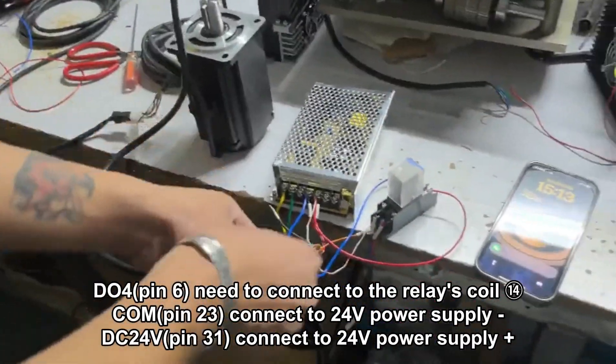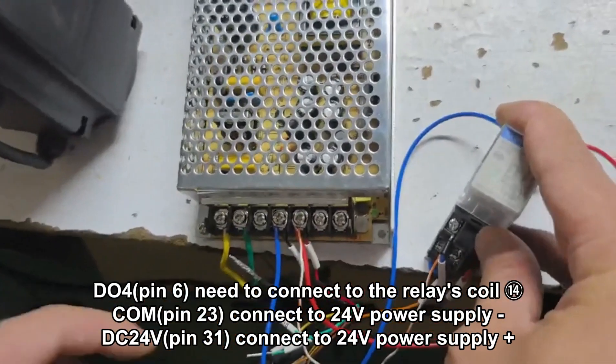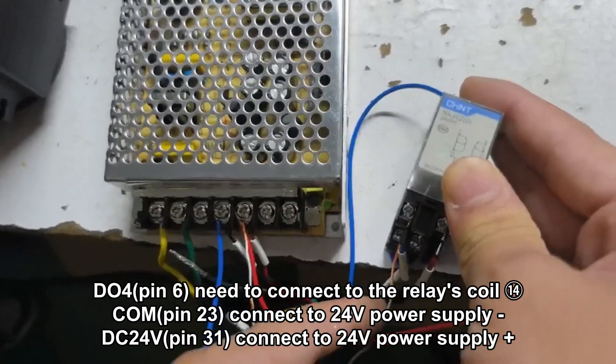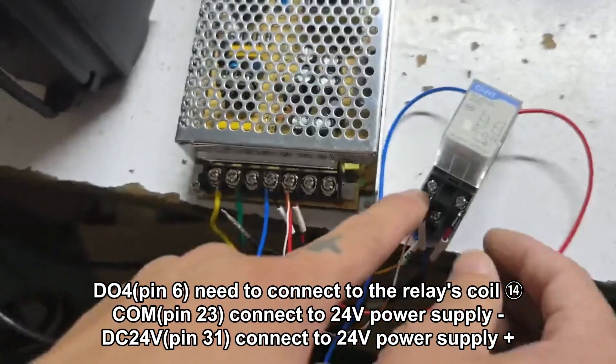DO4, which is pin 6, needs to connect to the relay's coil, which is pin 14. And COM, which is pin 23, connect to the 24V power supply negative. And DC 24V, which is pin 31, connect to the 24V power supply positive.